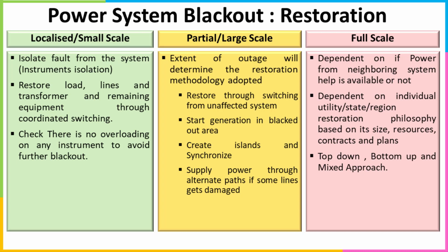So you can see in the full scale, how do you do restoration? Either you can start from basic scratch, like the restoration through the black start capable units. You bring those units, create a small island, and then synchronize them. The other option is that you can synchronize with whatever available power system has not been impacted.